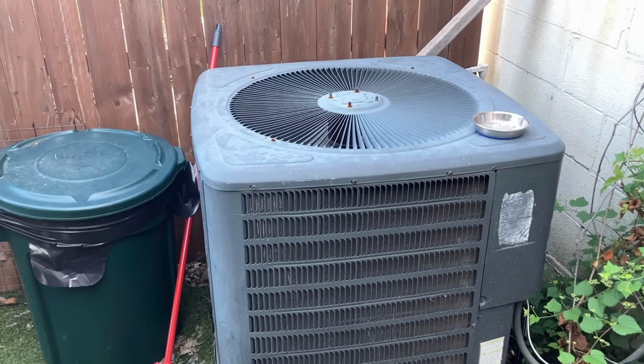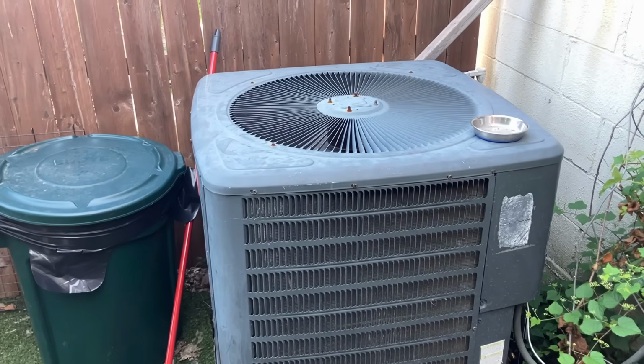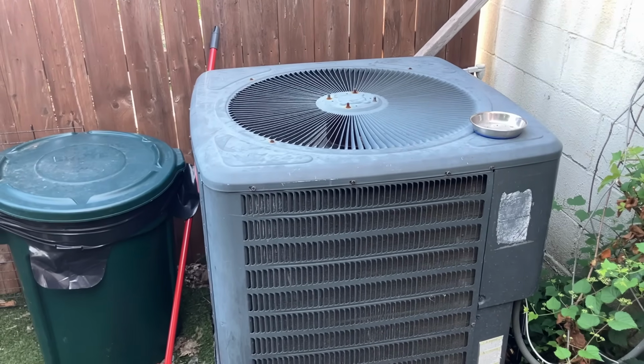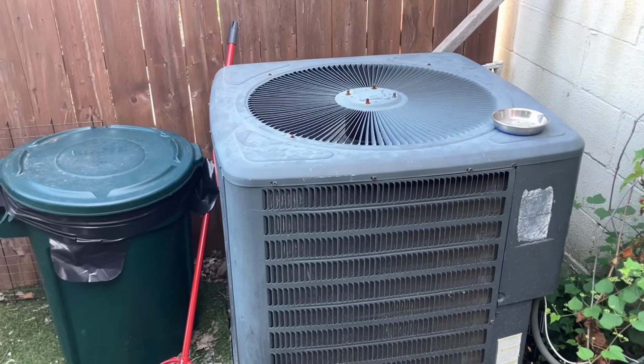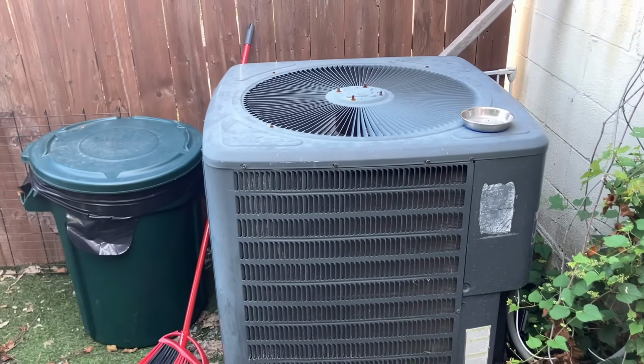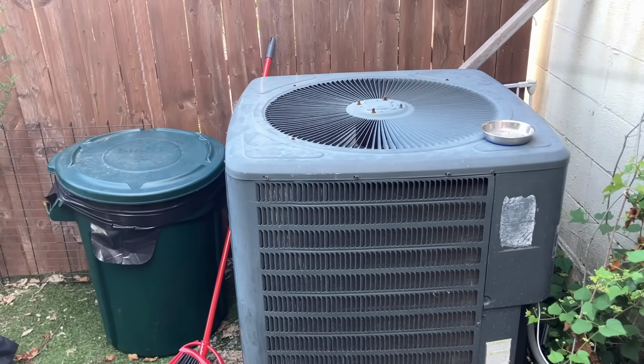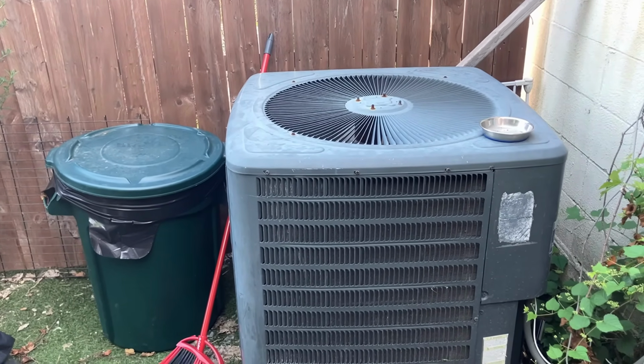Low superheat is not normally seen as a singular symptom. It usually occurs when the evaporator coil is flooded as a result of low airflow or refrigerant overcharge.